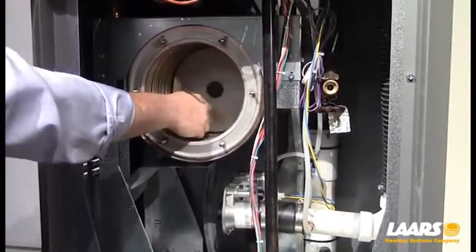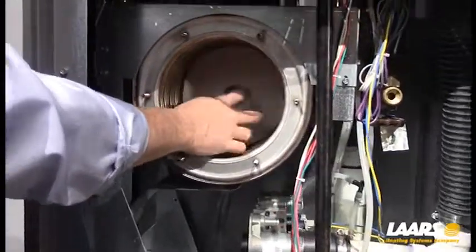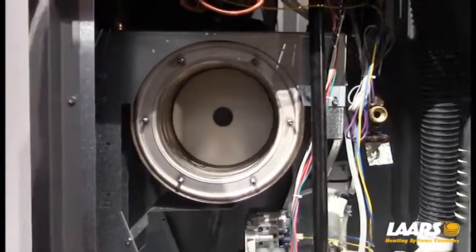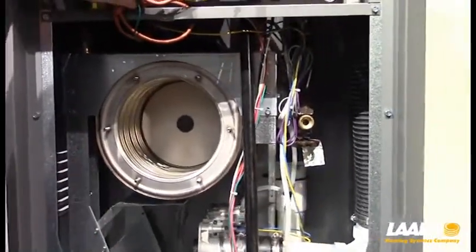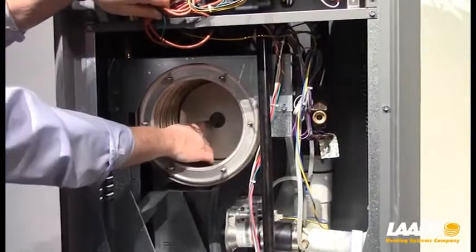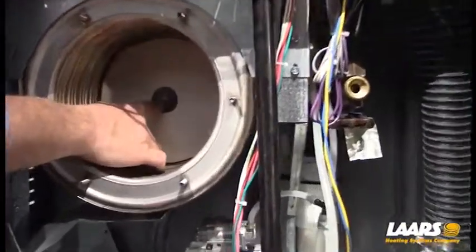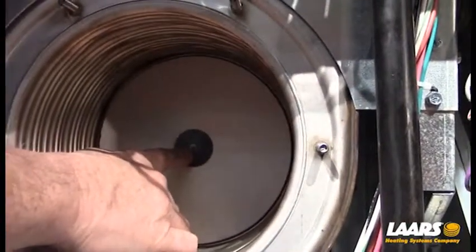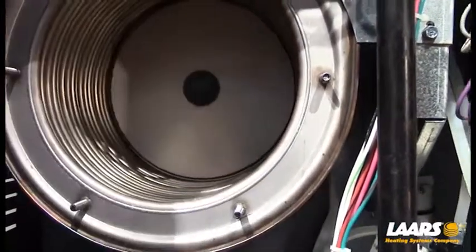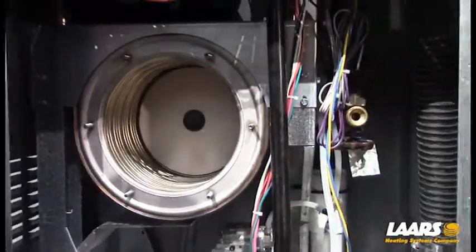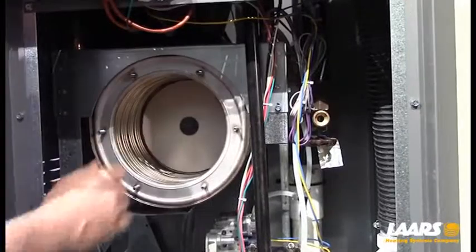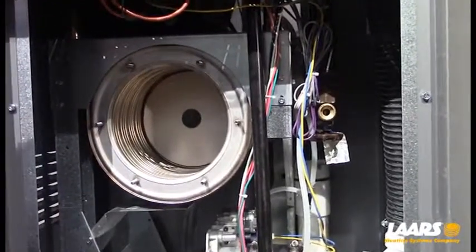Keep in mind we also have a back target wall that should not ever have to be removed, but if you damage it for any reason or it is damaged, there's a single Allen screw right there that would come out, and that rear target refractory wall would be replaced. So to clean this heat exchanger, you do not want to use a steel brush.